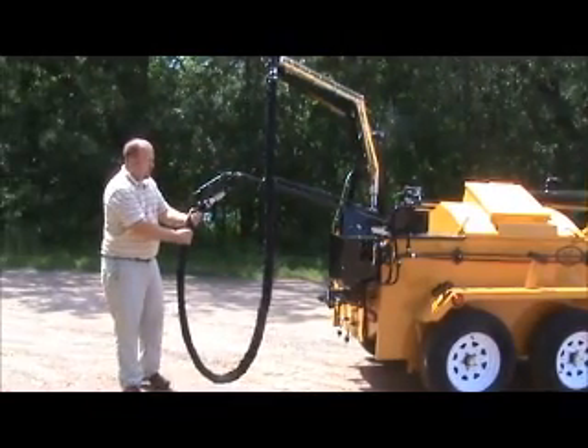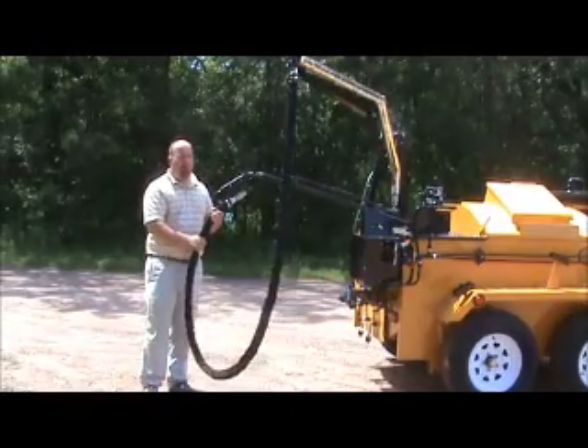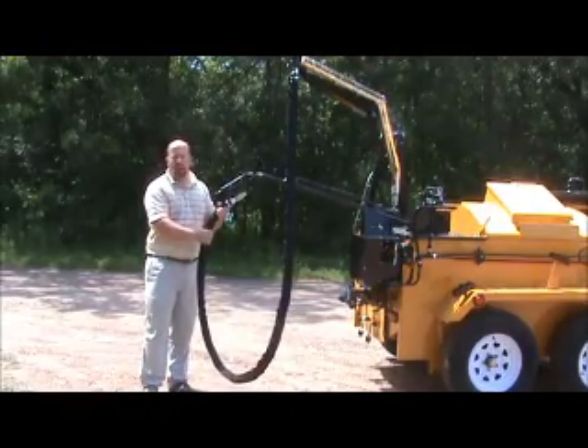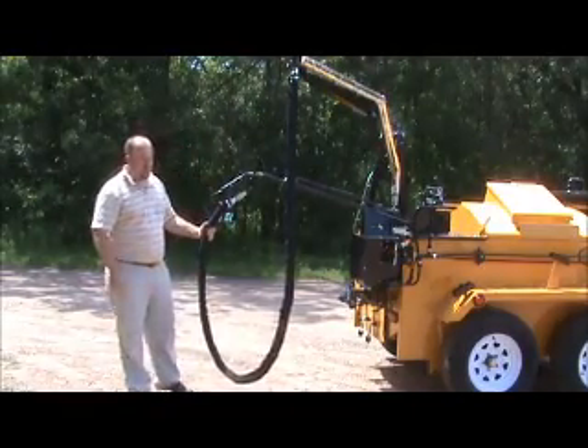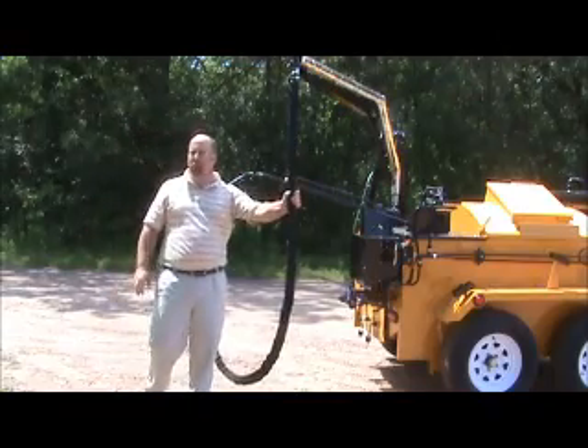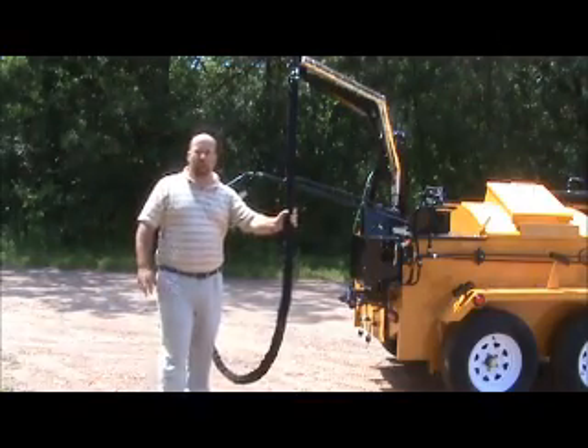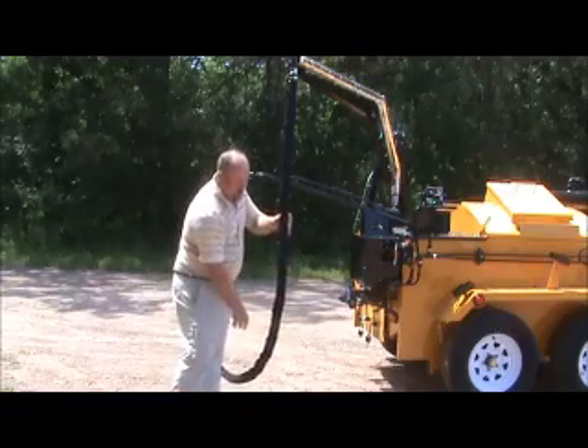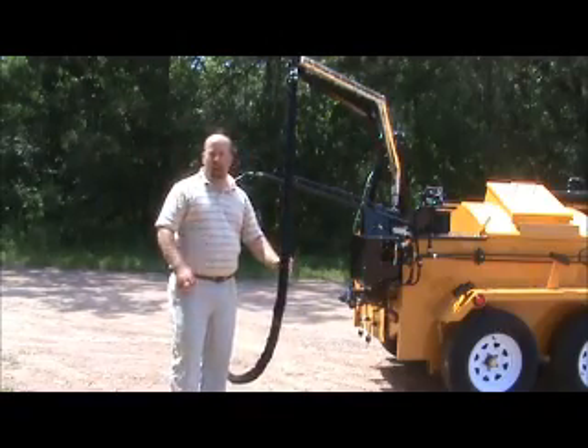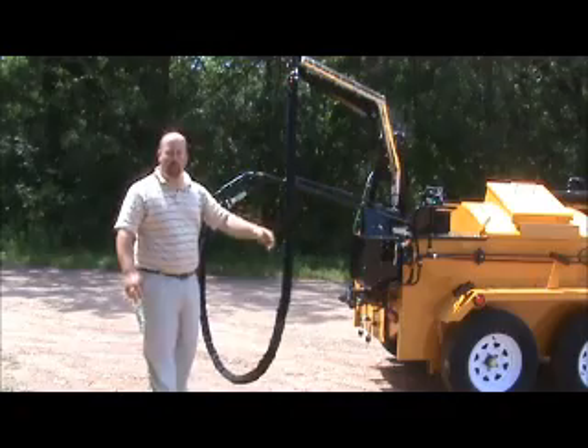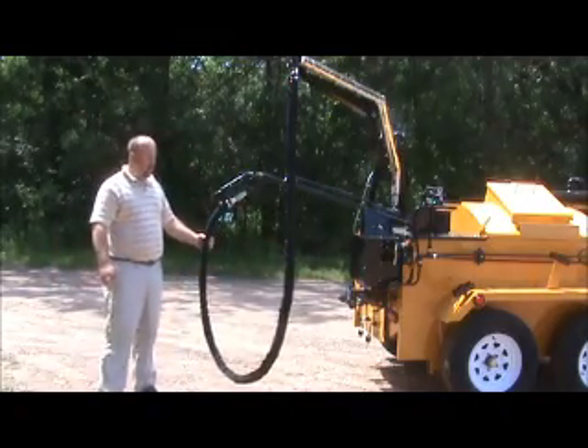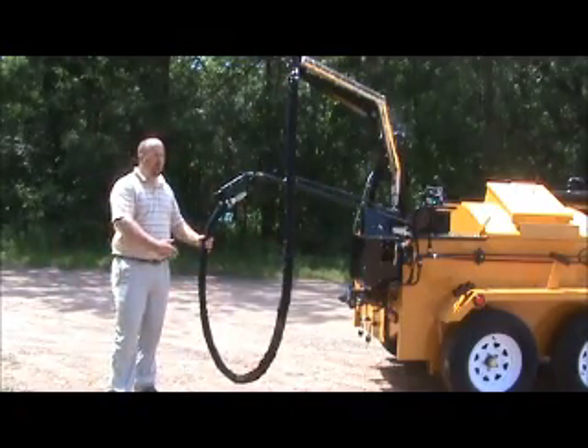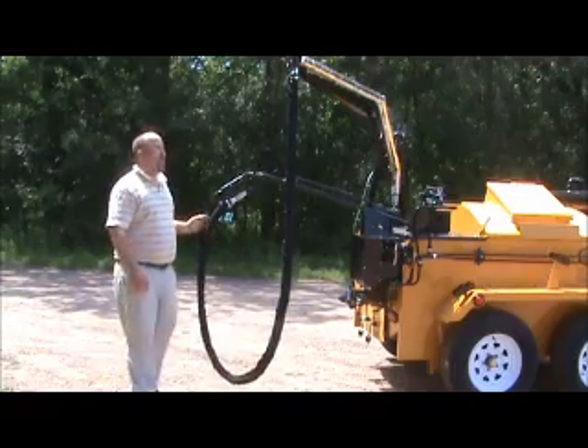The hose is a hot tar and asphalt hose. It's equipped with this fire jacket on here, guys. This is a safety device. Again, if the hose ruptures or if the hose develops a leak, it's going to fill this jacket up. If we drag the jacket off, obviously it's not going to do anything for protecting you guys. So you've got to kind of maintain that, keep an eye on that, so that you don't drag a hole through that jacket. It also protects the wires.